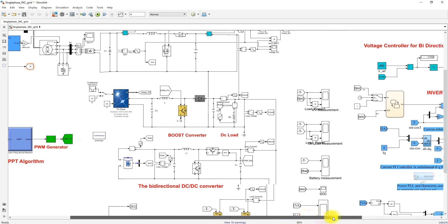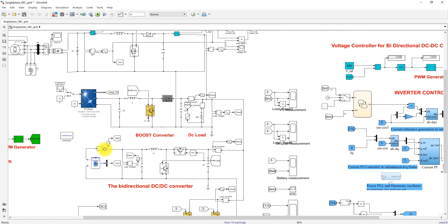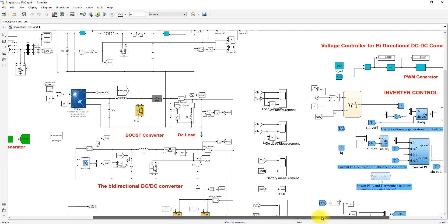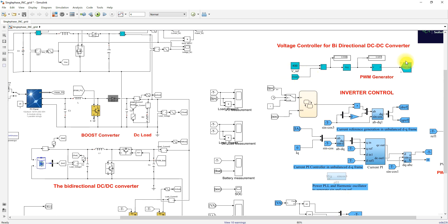Next we look at the battery energy storage system. The battery is connected to the DC bus via a bidirectional DC-DC converter. This bidirectional converter is used to maintain the DC bus voltage at a constant 400 volts, and it is controlled by means of a voltage control method.